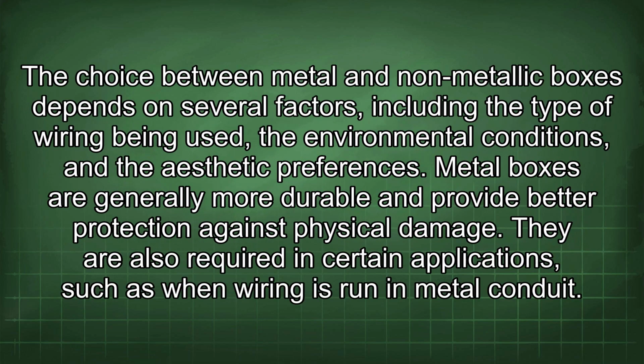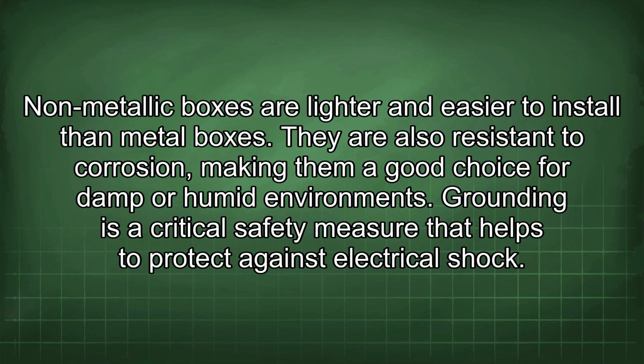The choice between metal and non-metallic boxes depends on several factors, including the type of wiring being used, the environmental conditions, and the aesthetic preferences. Metal boxes are generally more durable and provide better protection against physical damage. They are also required in certain applications, such as when wiring is run in metal conduit. Non-metallic boxes are lighter and easier to install than metal boxes. They are also resistant to corrosion, making them a good choice for damp or humid environments.